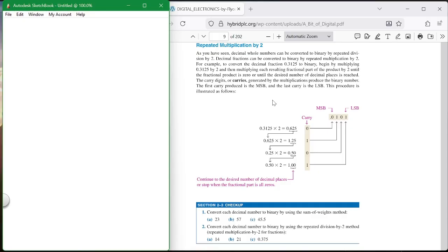If you have a number, what's the ideal way to handle any number in a computer? A real, okay? A real number. In other words, not an integer, but a real. Now, what's the downside of reals? They're accurate to 7 places. Well, that should be good enough, right? 7 places is good enough. If you have an extremely large count, sometimes it's not. And if you want to use a counter or a time-based, that type of thing, usually when you're counting in whole numbers, integers are okay.